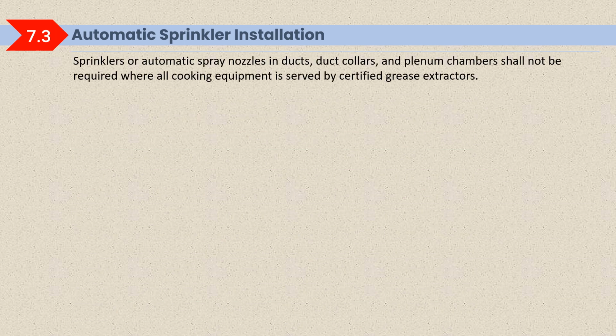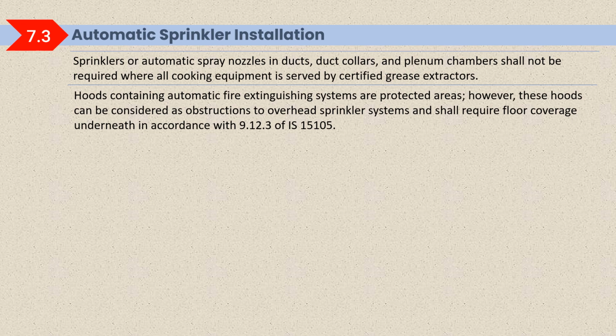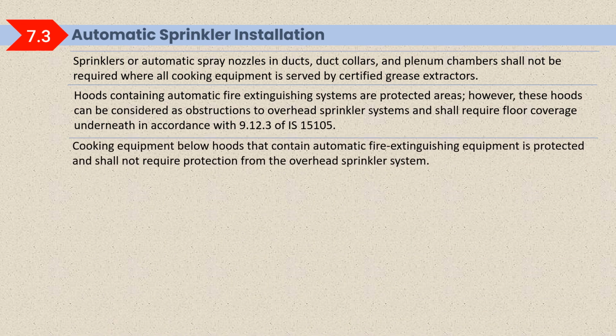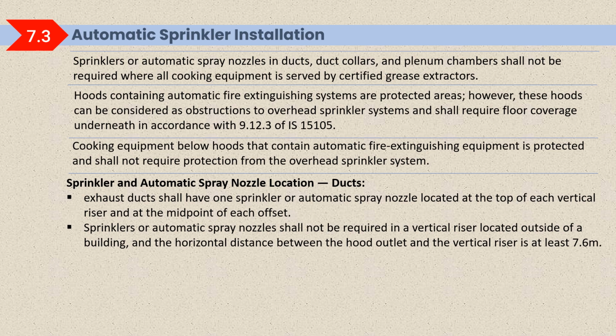Sprinkler or automatic spray nozzle in duct collar and plenum chamber shall not be required where all cooking equipment is served by certified grease extractor. Hoods containing automatic fire extinguishing system are protected areas. However, these hoods can be considered as obstruction to overhead sprinkler system and shall require floor coverage underneath in accordance with IS 15105. Cooking equipment below hoods that contains automatic fire extinguishing equipment is protected and shall not require protection from the overhead sprinkler system.